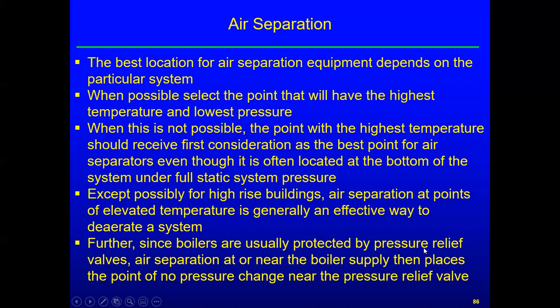The best location for our air separation equipment depends on the particular system. When possible, select the point that will have the highest temperature and lowest pressure. We said that. When this is not possible, the point with highest temperature should receive first consideration as the best point for air separators, even though it is often located at the bottom of the system under full static pressure. So if you got to select between the two of them, go to the point of highest temperature before you go to the point of highest pressure for your air separation point.